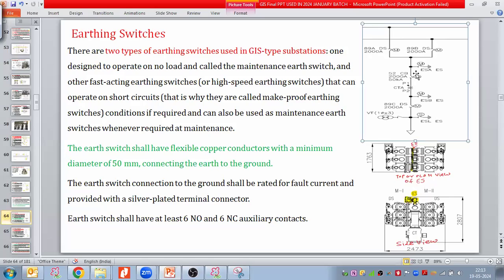Insulating link here. Then breaker, CT, then disconnectors with two earthing switches, one on the breaker side. So there should be one insulating link over here as well. And then the outgoing line, and then S is representing the high speed earthing switch. And here we have maintenance. M is representing the maintenance earthing switches.